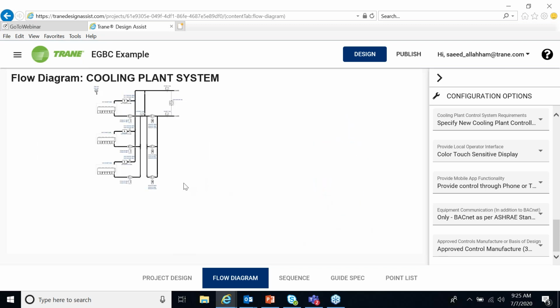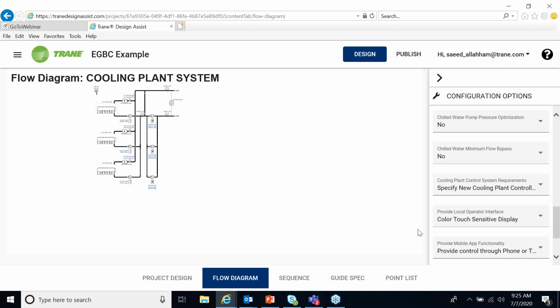And in the flow diagram, we see 3 chillers. We have 3 primary pumps. We have 3 secondary pumps. And since the pumps are controlled by variable speed drive, we have the pressure sensor or transducer, which is controlling the speed of the secondary pumps. And now, whatever changes we make here will be reflected here immediately.